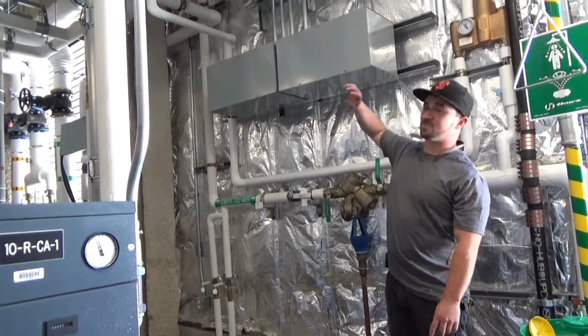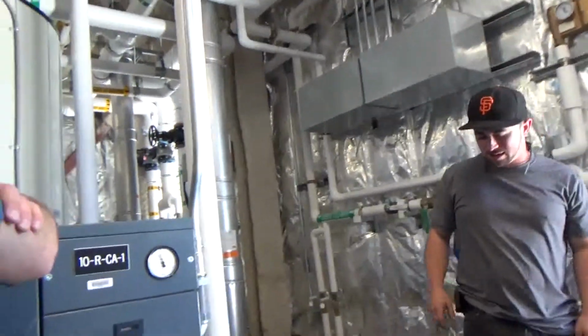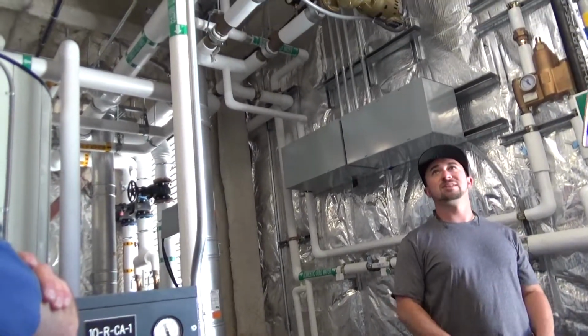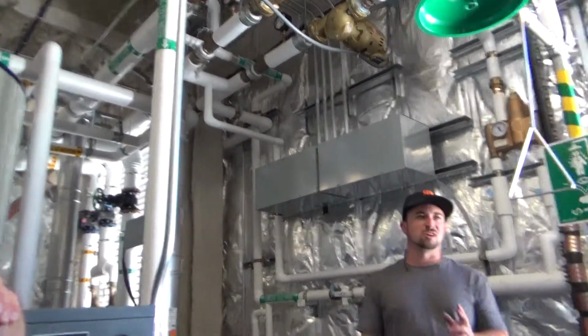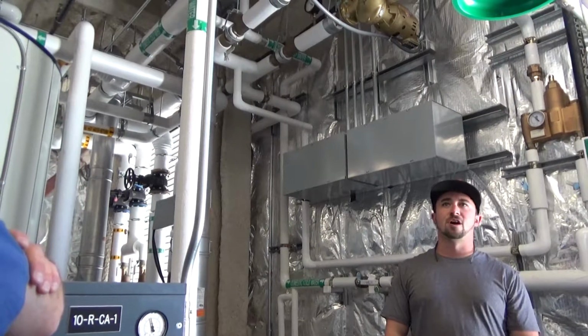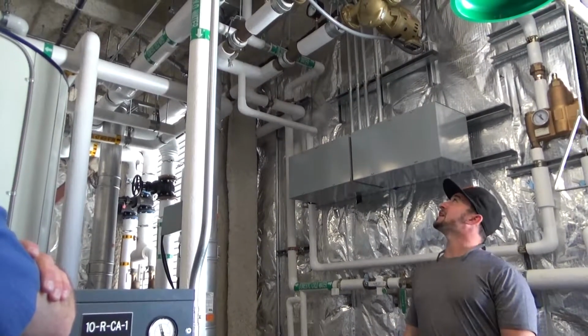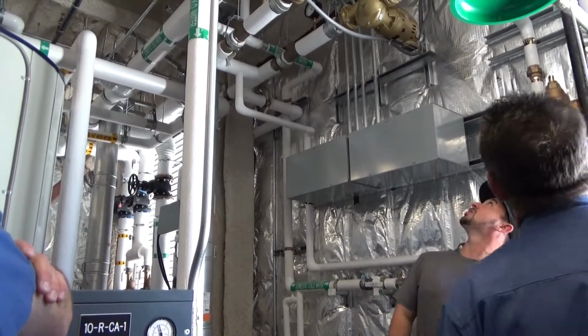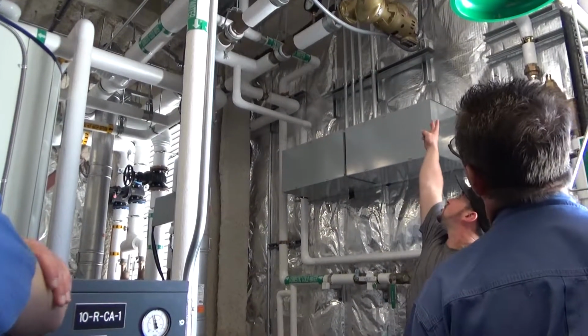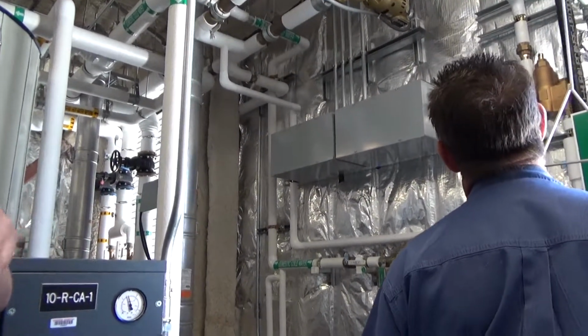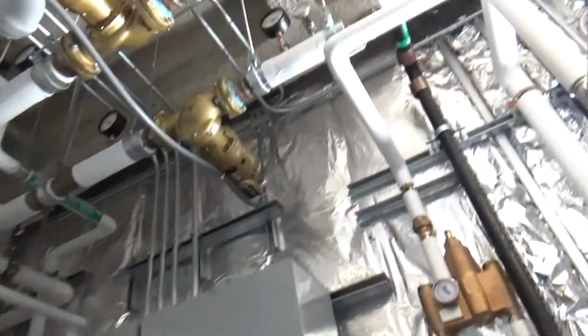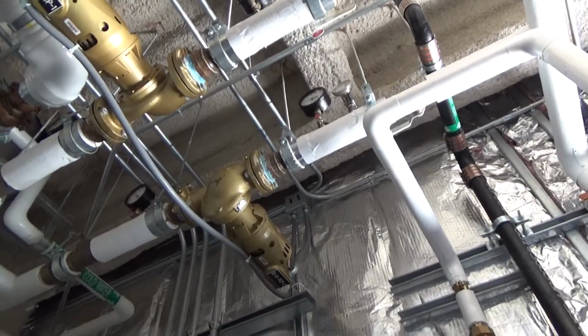I don't know what's controlling these. That's not my scope, but I think they said it was just straight across the line, so it's not on a VFD, so it's just on-off. I'm assuming it's on some sort of heat timer, so there's a sensor somewhere. Oh yeah, there's two switches right there. I'm assuming there's a sensor somewhere that senses a drop in temperature in the loop, kicks those pumps on, gets that temperature back up, and then they shut back off.